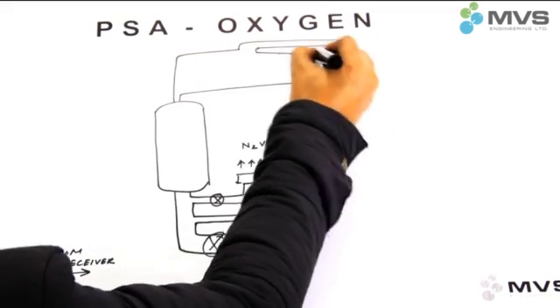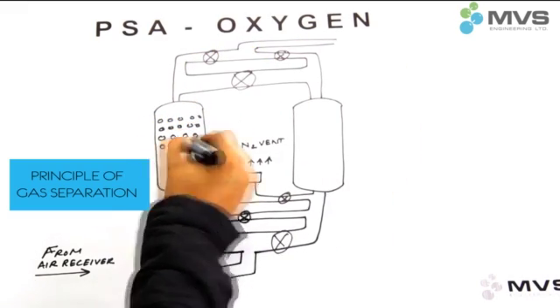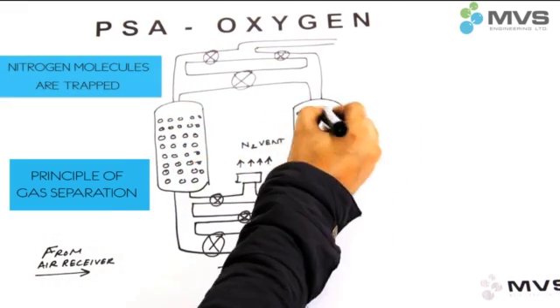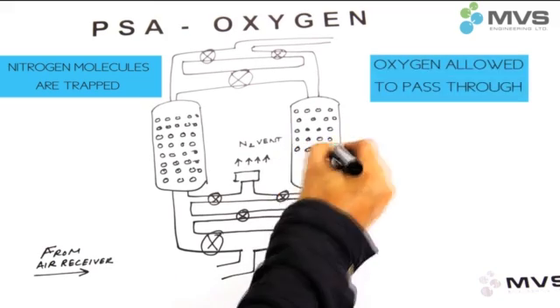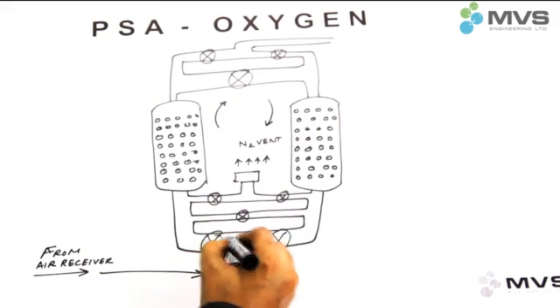PSA oxygen generation technology works on the principle of gas separation by passing air through molecular sieves where nitrogen molecules are trapped and oxygen is allowed to pass through. PSA technology comprises two towers filled with alumina and molecular sieves.